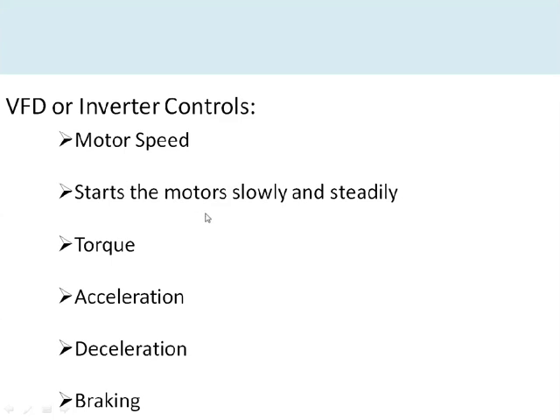In addition to varying speed, the VFD can also start the motor slowly and steadily. Without a VFD, motor starting current is very high — generally six times the rated current — so starters such as a star-delta starter or soft starter are needed. If you use a VFD, there is no need for any starters. It also controls torque and acceleration, and provides braking capability for the induction motor.